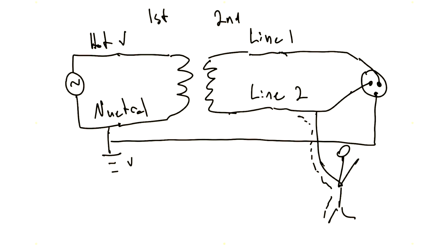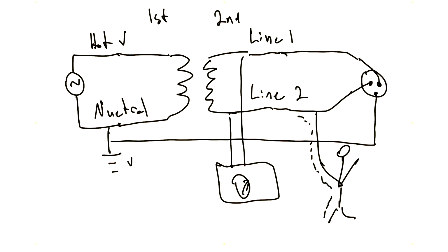then there's no issue. Now there is an absolute potential for hazard and your line isolation monitor is going to go wild. So where's the line isolation monitor in this? Well, I haven't drawn it yet. So the line isolation monitor we'll put down here. And the line isolation monitor is connected to both line 1 and line 2. And it's grounded.